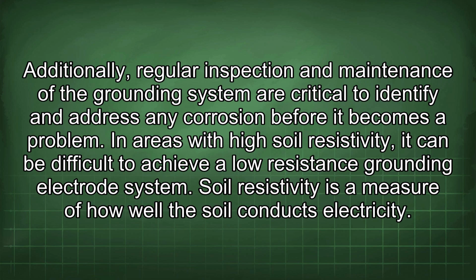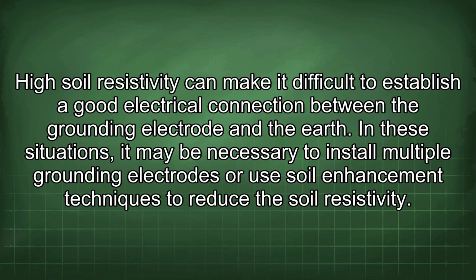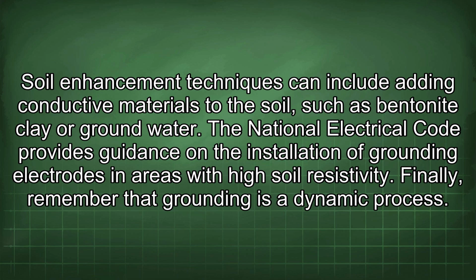In areas with high soil resistivity, it can be difficult to achieve a low-resistance grounding electrode system. Soil resistivity is a measure of how well the soil conducts electricity. High soil resistivity can make it difficult to establish a good electrical connection between the grounding electrode and the earth. In these situations, it may be necessary to install multiple grounding electrodes or use soil enhancement techniques to reduce the soil resistivity. Soil enhancement techniques can include adding conductive materials to the soil, such as bentonite clay or groundwater. The National Electrical Code provides guidance on the installation of grounding electrodes in areas with high soil resistivity.